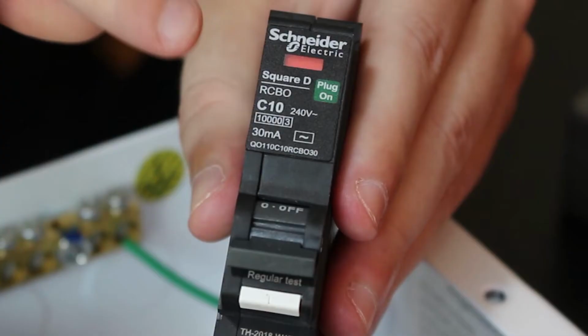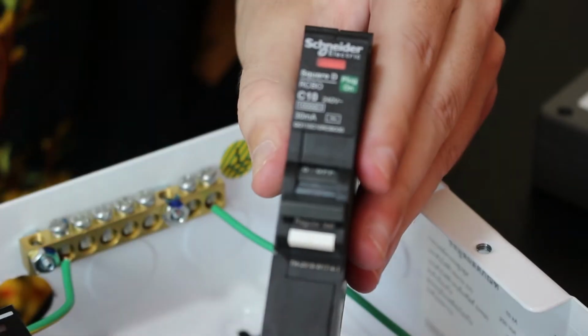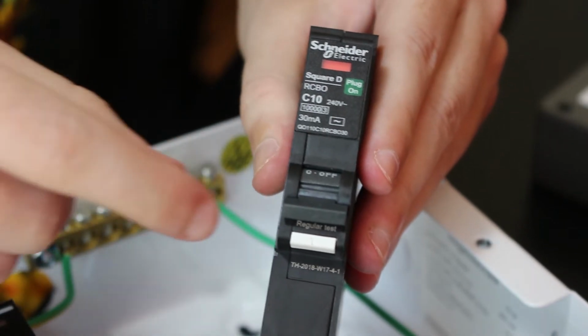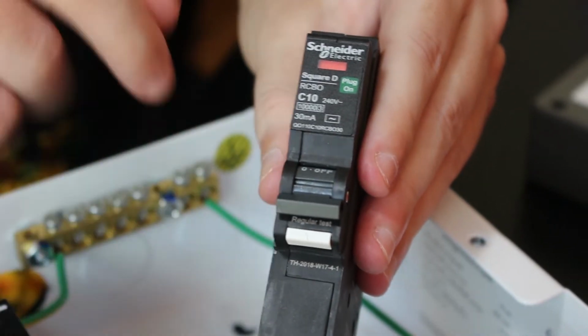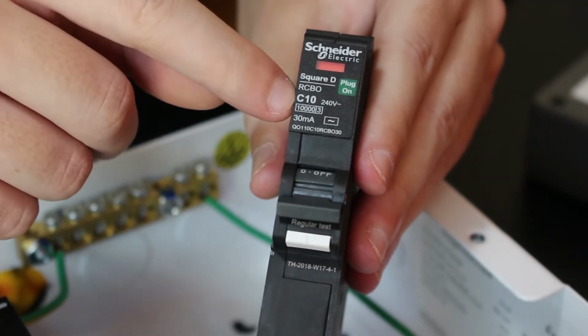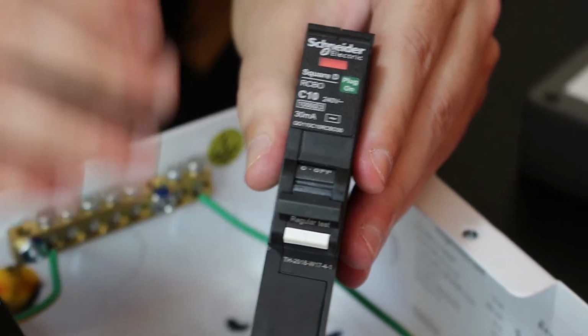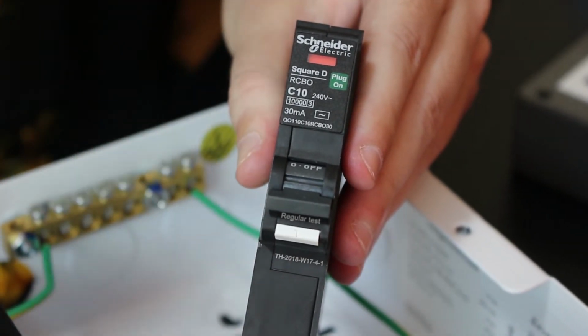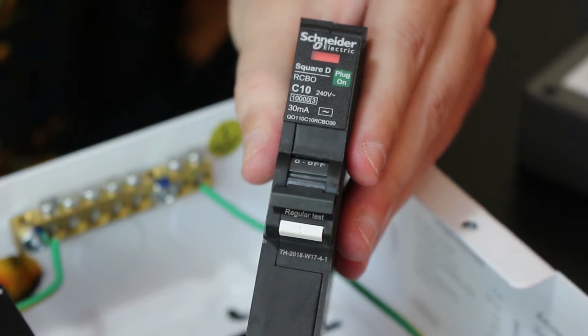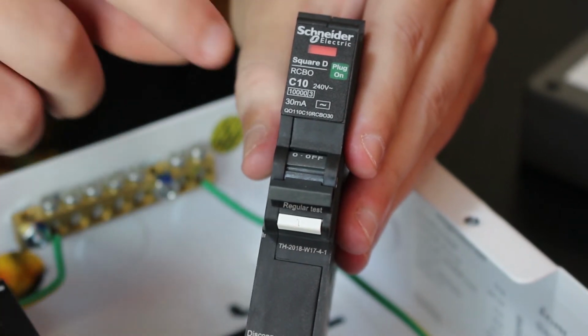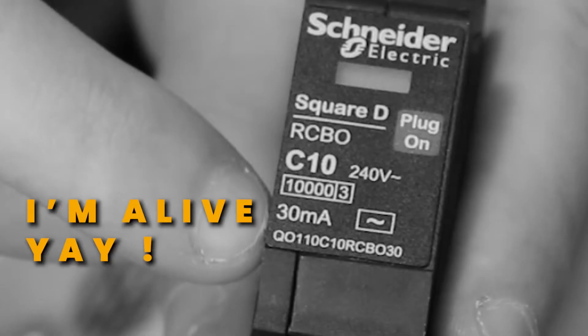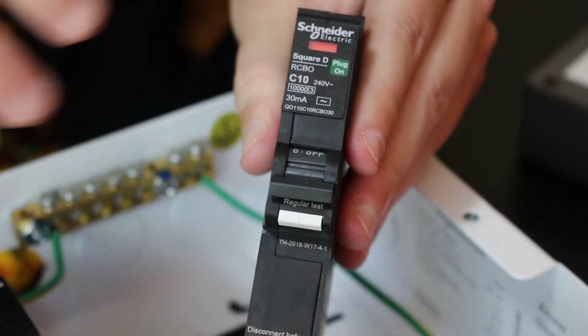The second type of circuit breaker is going to be that one, an RCBO, which is a little bit more advanced and a lot more expensive. But this one is also C10, so it's also going to cut at more than 10 amps if those 10 amps go into your circuit, but also it's going to cut at 30 milliamps if that current goes out of where it should be.